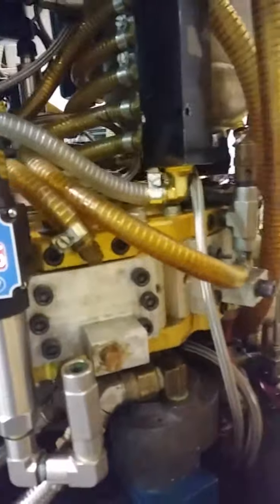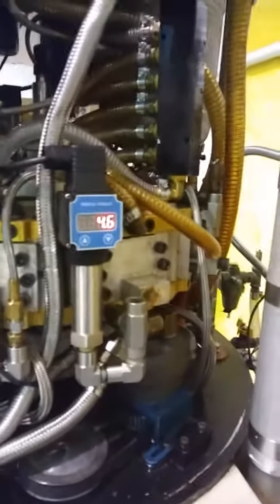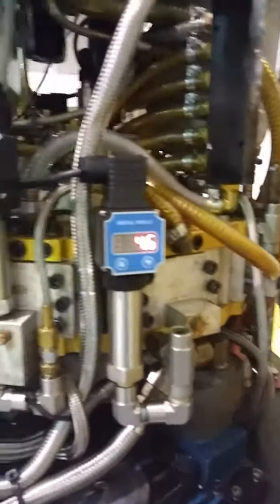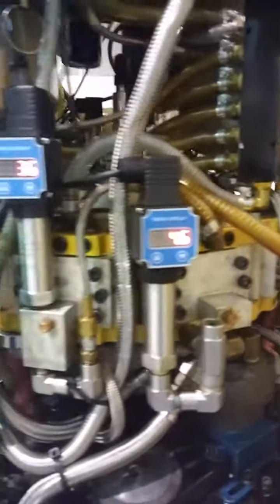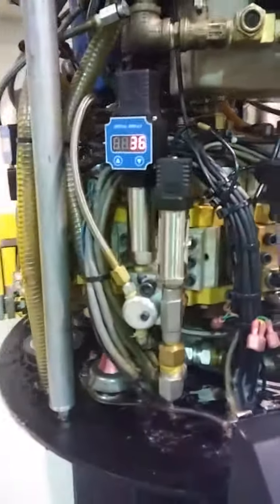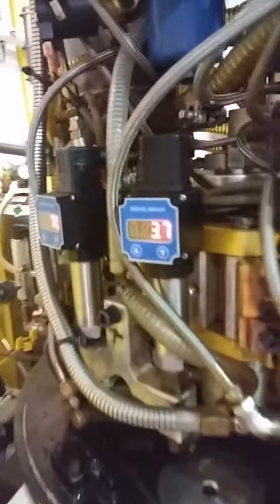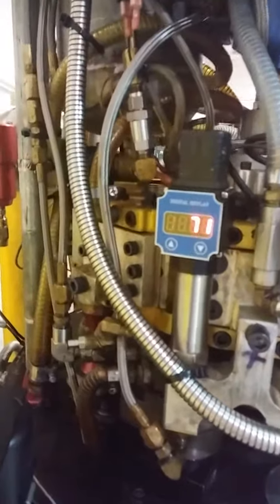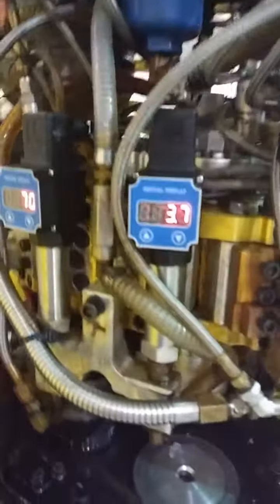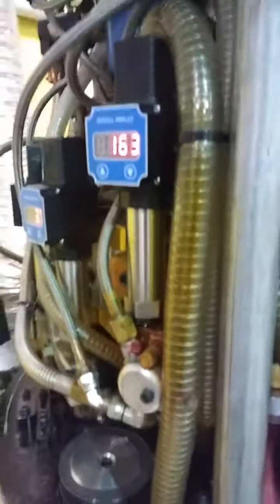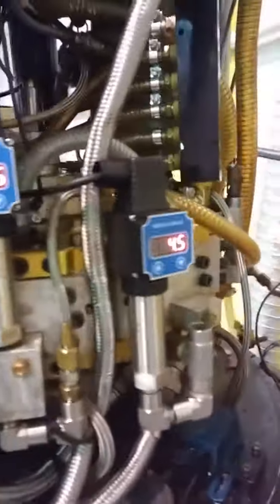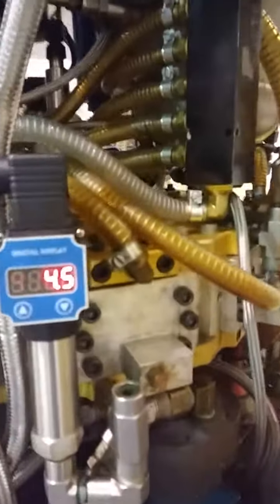So every stage, of course, has mechanical pressure relief valves. And this is a 10-piston system that I developed, which is radial based, and it's quite compact actually for its performance. Maybe 20 inches in diameter and about 6 inches high, and it puts out a lot for its size, and it runs at very high velocities. We're able to tightly control everything because of its small size.